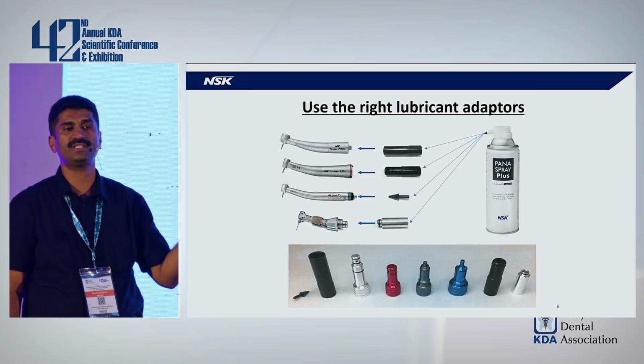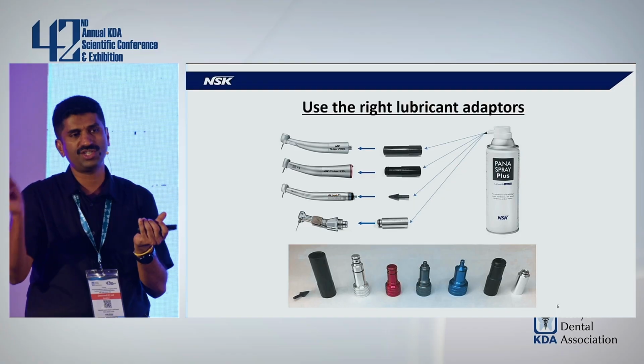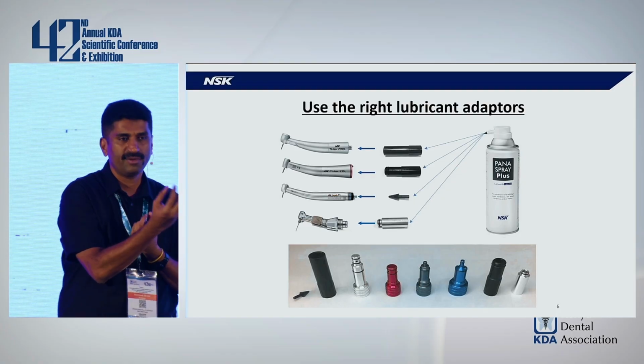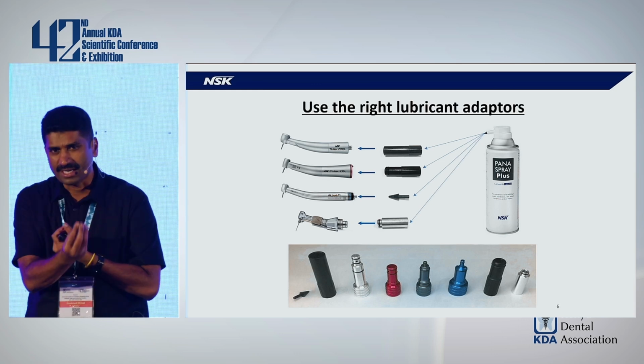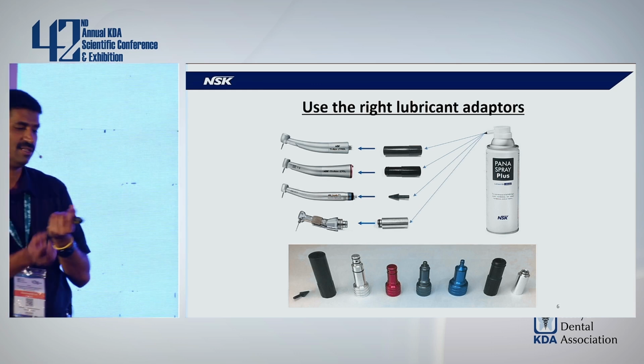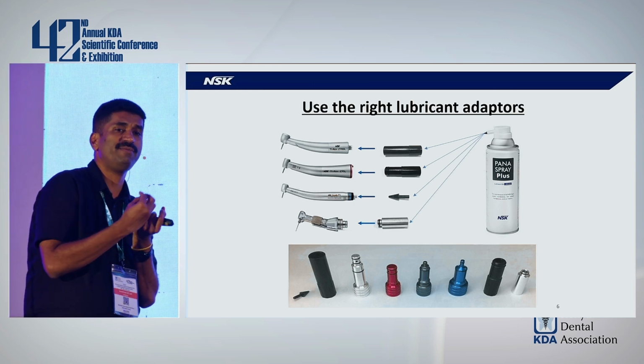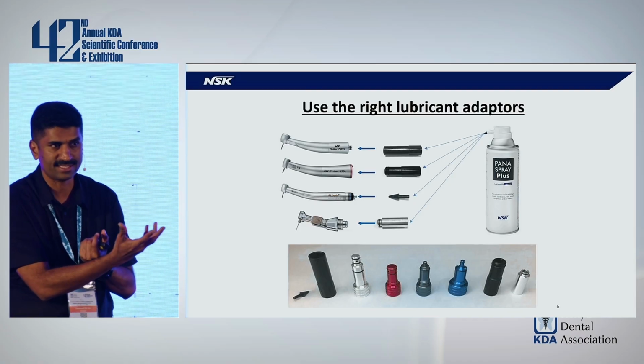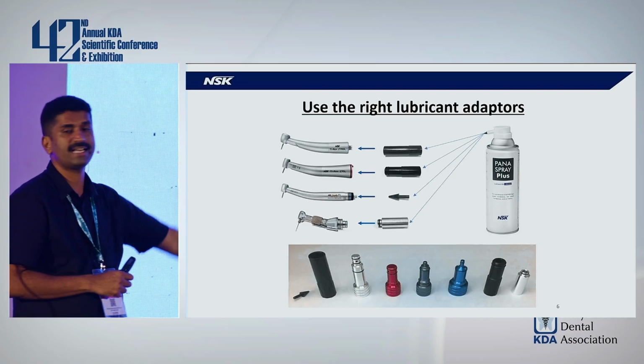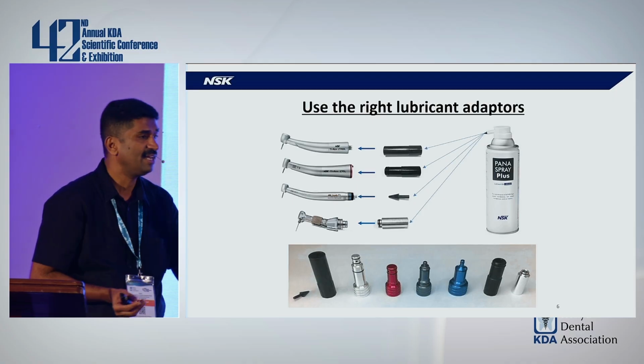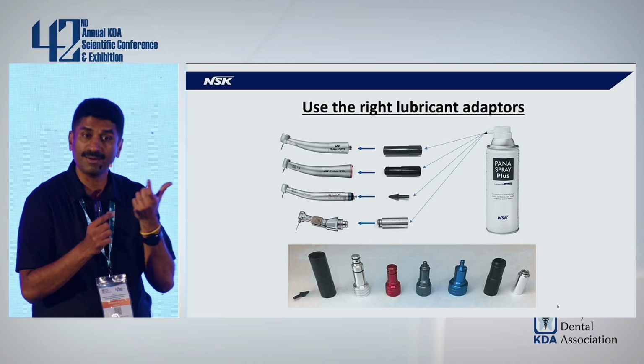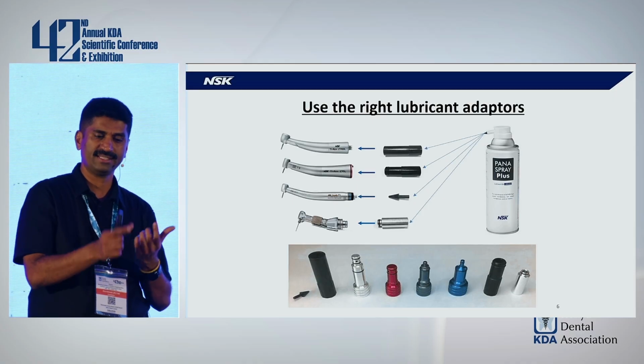If you do not use these adapters and if you just lubricate using an oil spray, the oil will never reach the required parts which need to be lubricated. What I mean to say is the oil will never reach the head part of the handpiece unless you use these adapters. Where to find these adapters? Each and every handpiece box comes with this adapter. It's as simple as that.